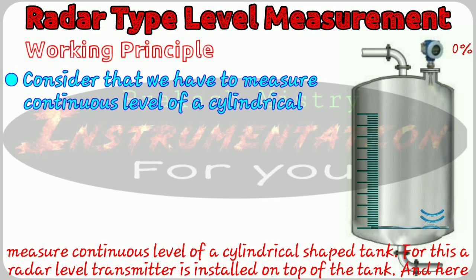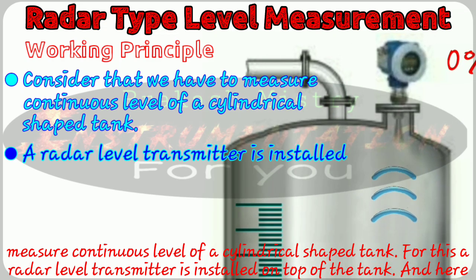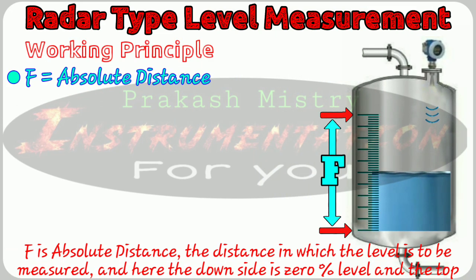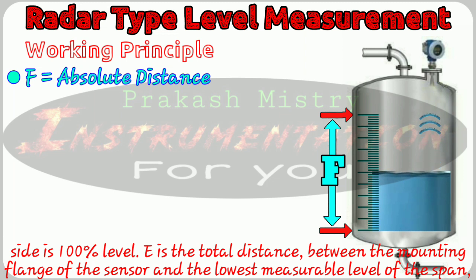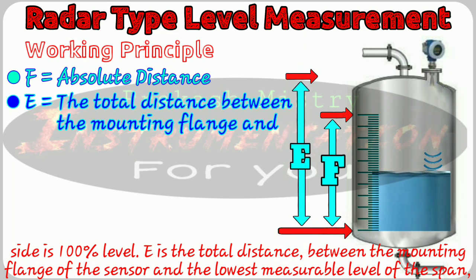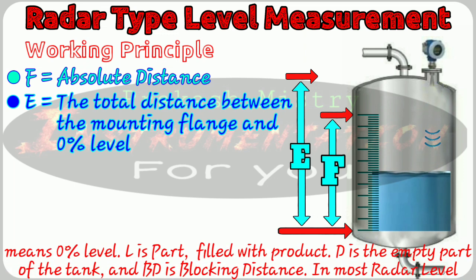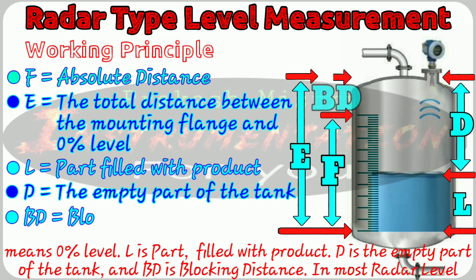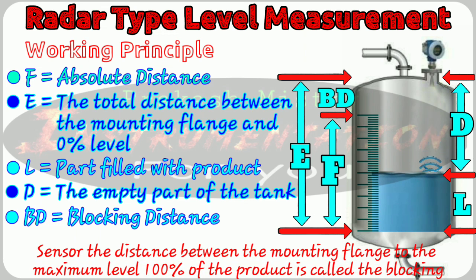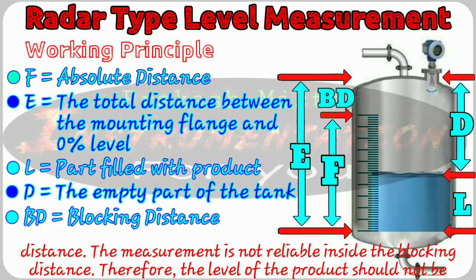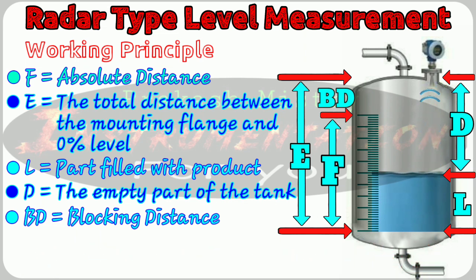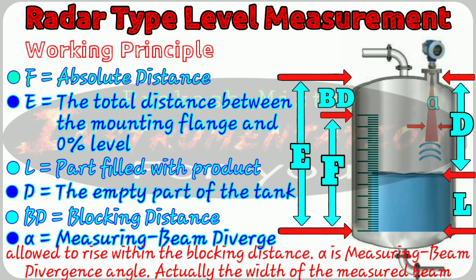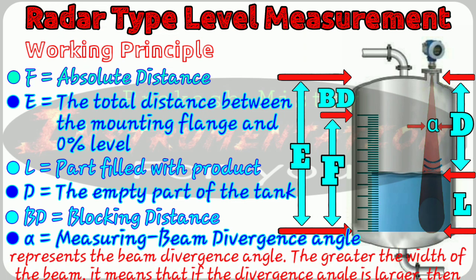Consider that we have to measure the continuous level of a cylindrical shaped tank, with a radar level transmitter installed on top. Here, F is the absolute distance — the distance in which the level is to be measured. The downside is the 0% level and the top side is the 100% level. E is the total distance between the mounting flange of the sensor and the lowest measurable level of the span, meaning 0% level. L is the part filled with the product, D is the empty part of the tank, and BD is the blocking distance. In most radar level sensors, the distance from the mounting flange to the maximum 100% level is called the blocking distance, and measurement is not reliable inside it. Therefore, the level of the product should not be allowed to rise within the blocking distance.